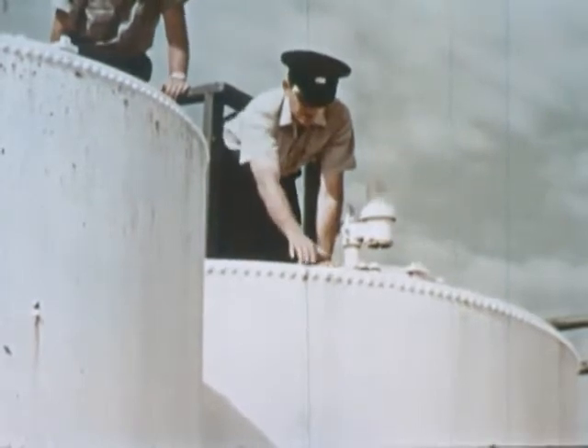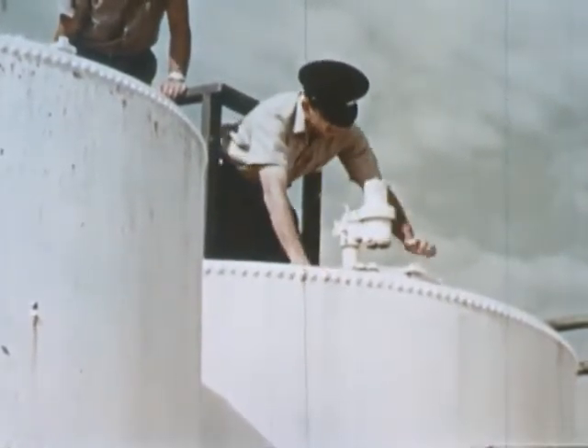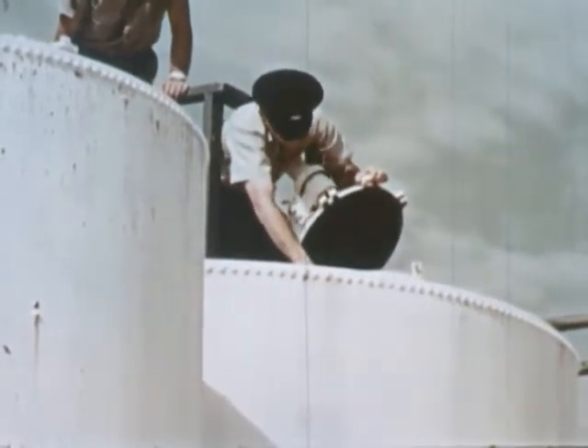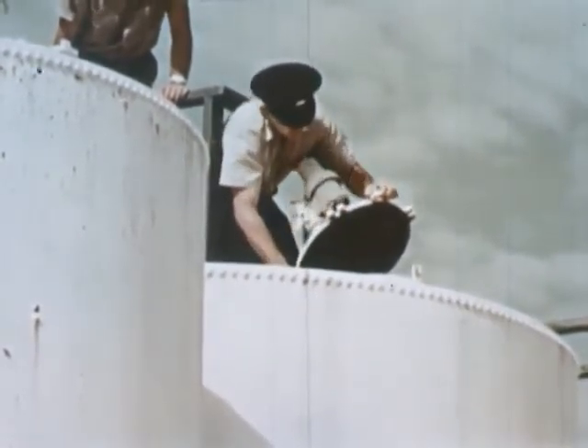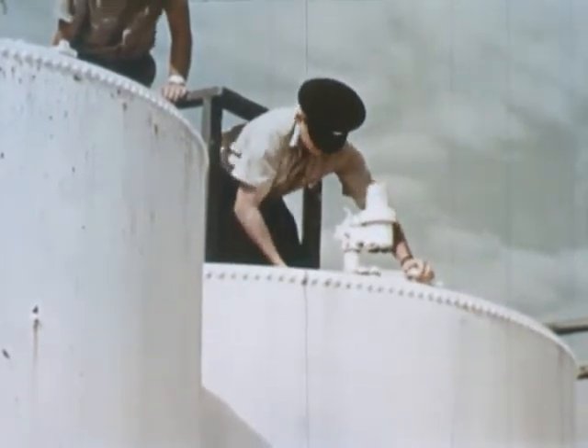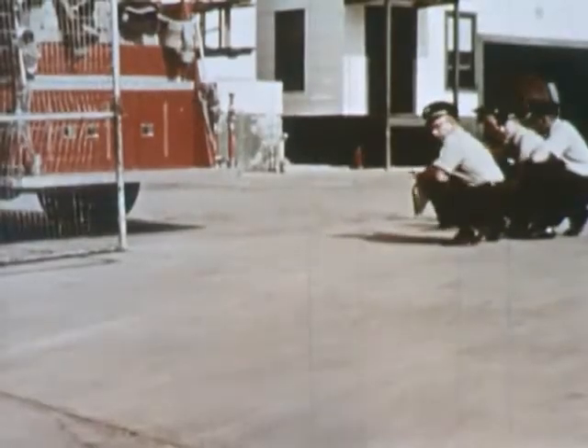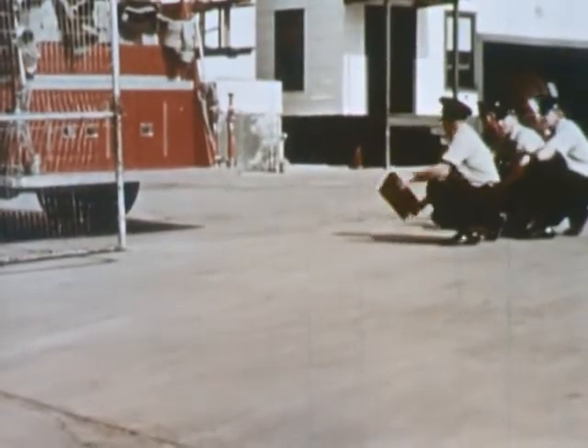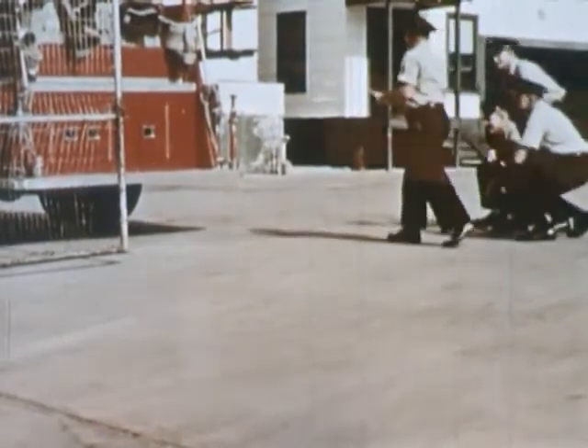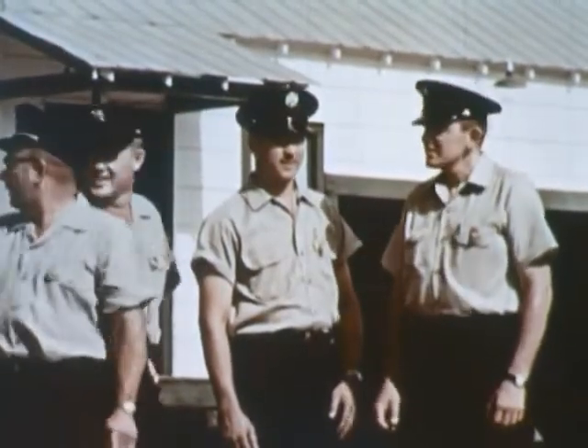Emergency venting may be provided by single large vents, additional vents, or loose manhole covers. Small normal breather vents permit filling and emptying or compensate for sudden temperature changes. The slope of the ground is an important factor, controlling the flow of burning liquid, which might affect hose lays or accessibility to hydrants.